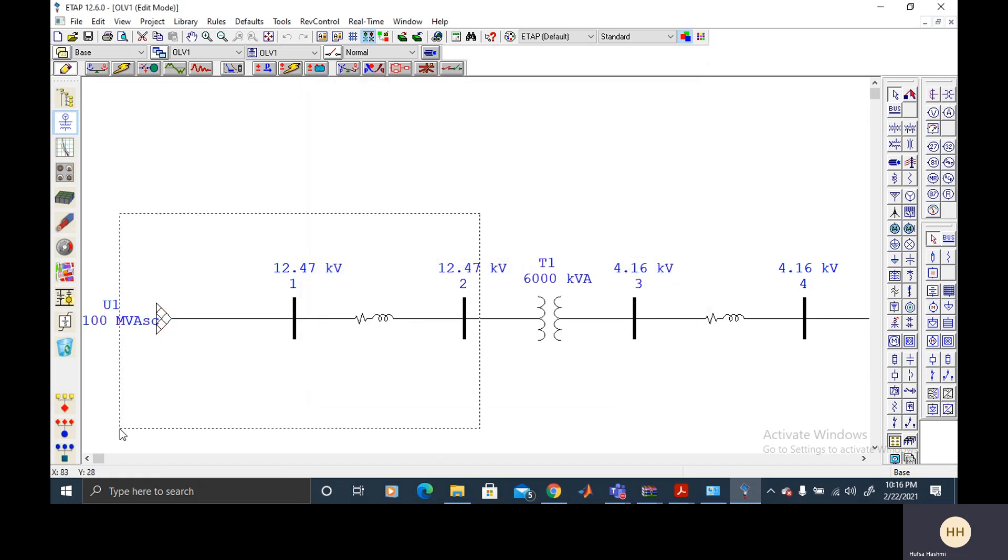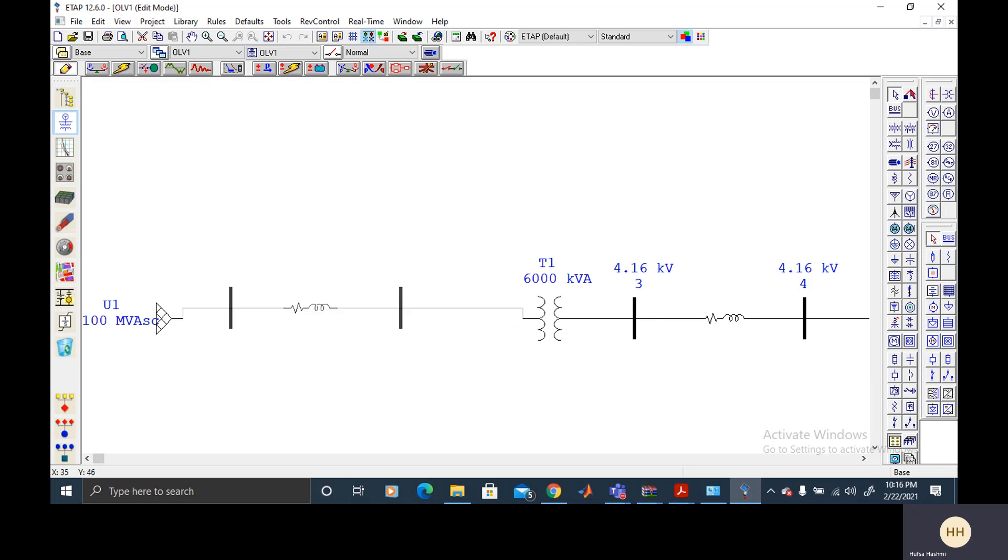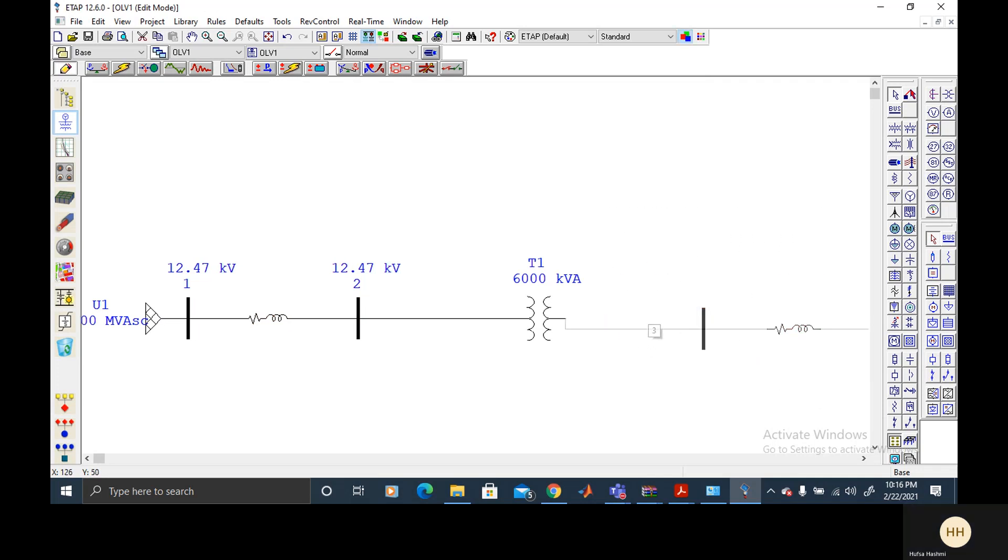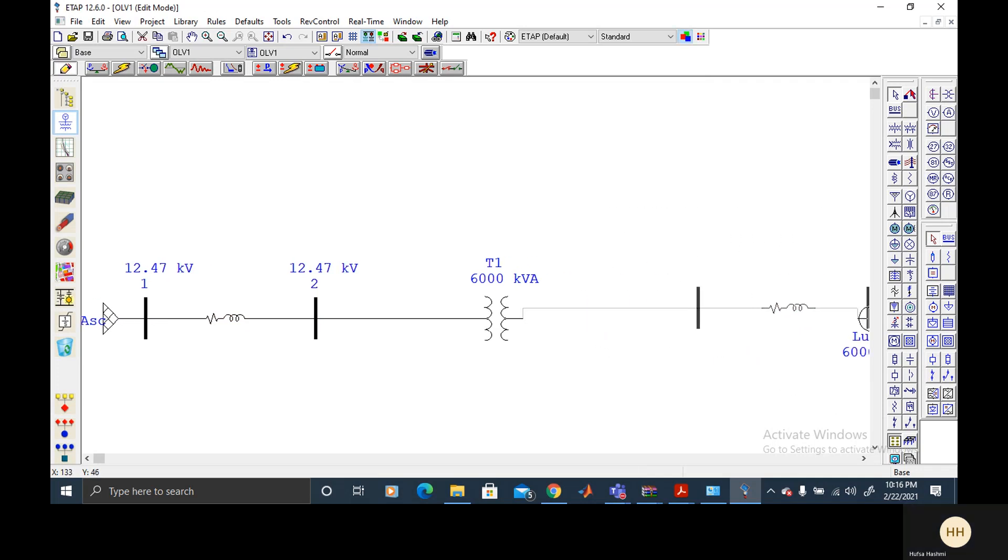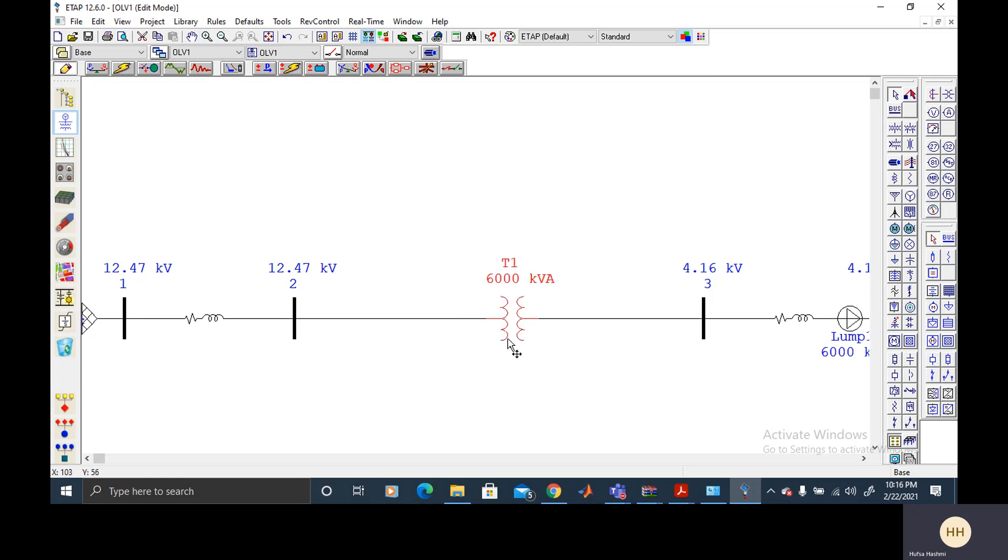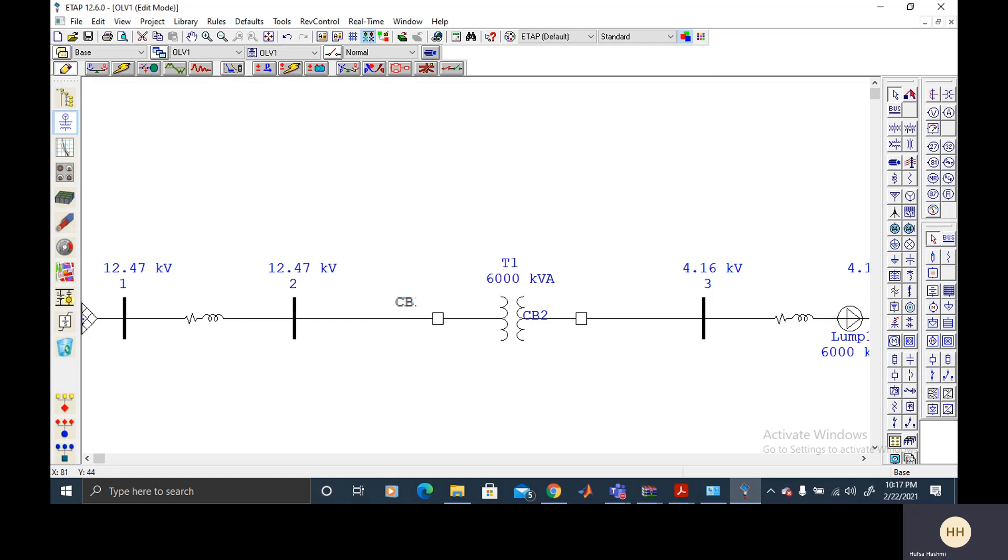And then we are going to do the differential protection of the transformer. First, we are making one folder for the protective devices. So in differential protection, we need to isolate the protected equipment. So for that, we will add high voltage circuit breakers on either side. And just move the ID above it to avoid confusion. You can just drag and drop the ID.